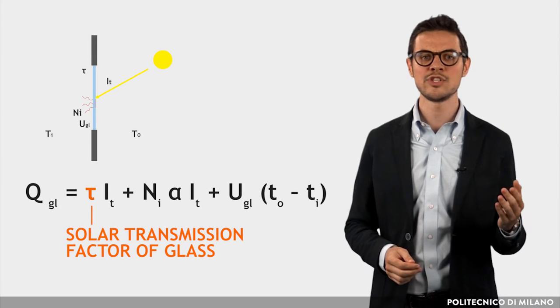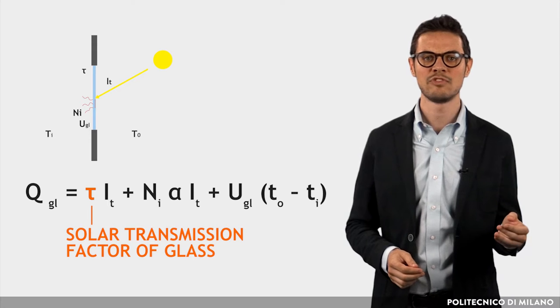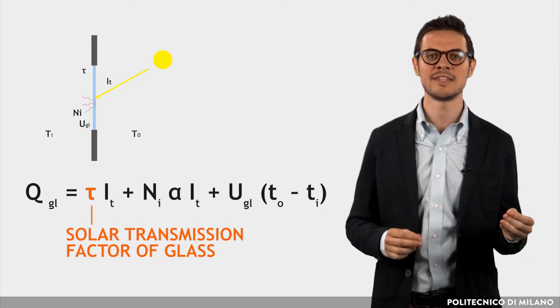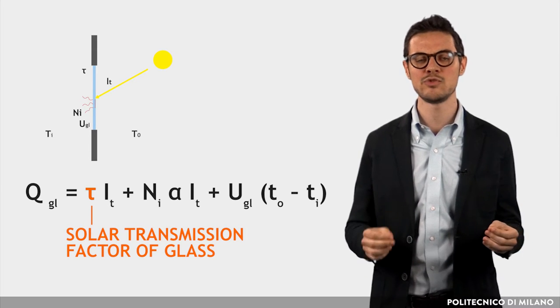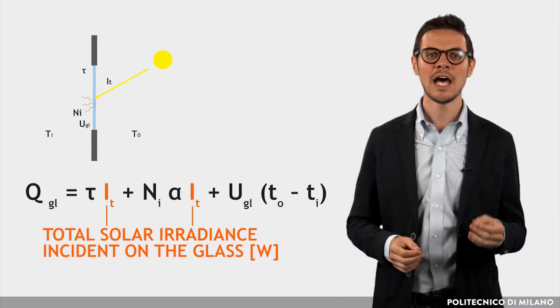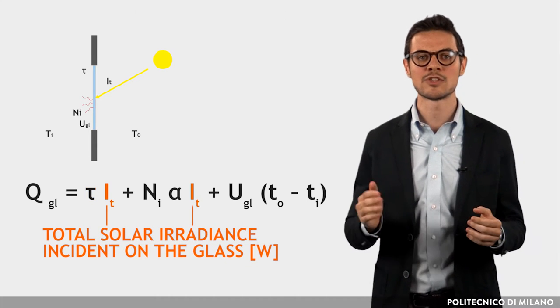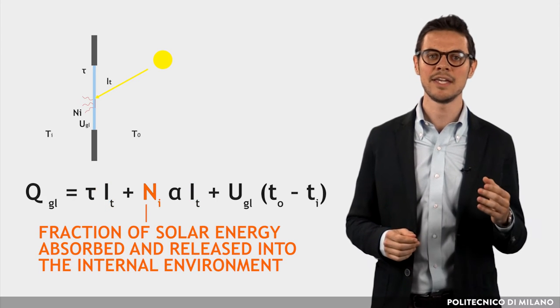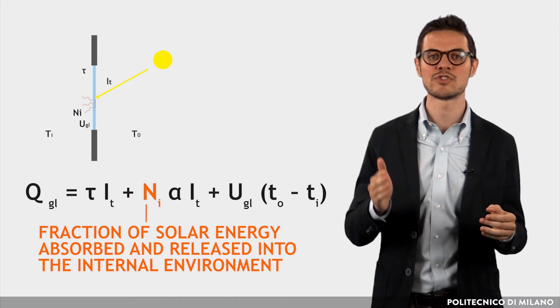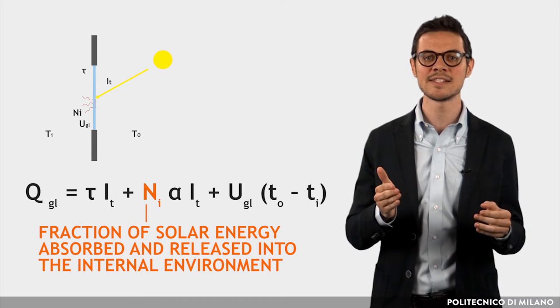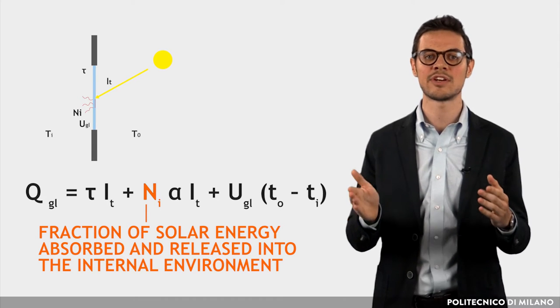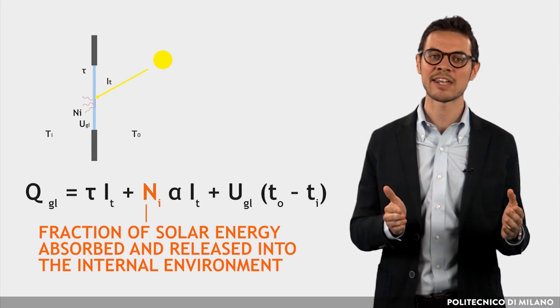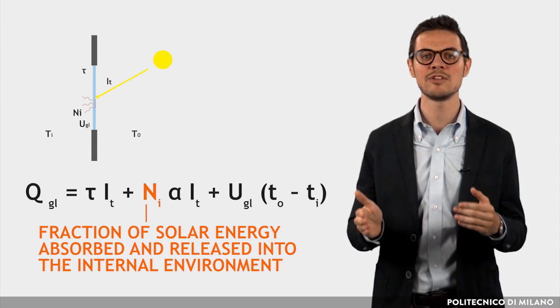Tau is the solar transmission factor of glass, function of the incident angle of solar beam and diffuse radiation. I_t is the total solar irradiance incident on the glass in Watts. And N_I represents the fraction of solar energy absorbed by the glass and released into internal environment by radiation in the far infrared and convection.